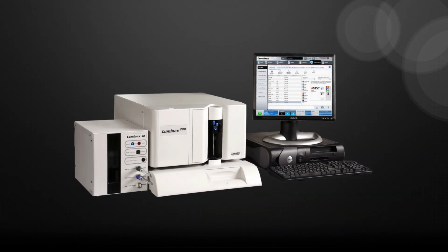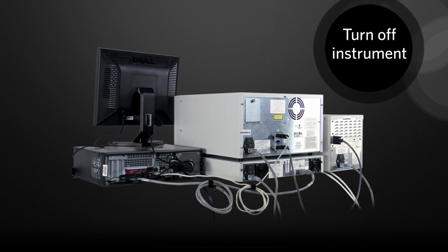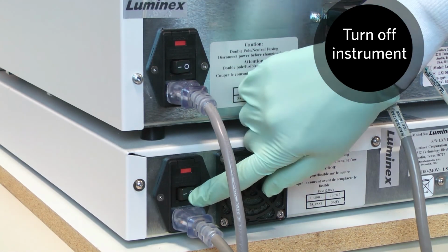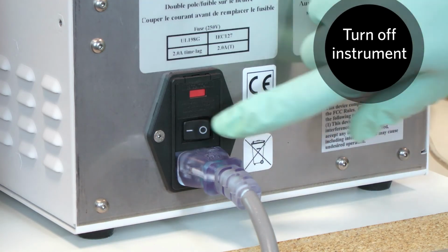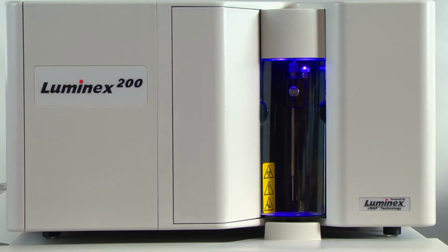After the routine finishes running, turn off the Luminex 200 analyzer, XY platform, and, if used, the sheath delivery system.